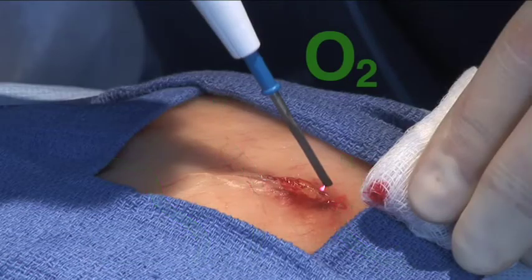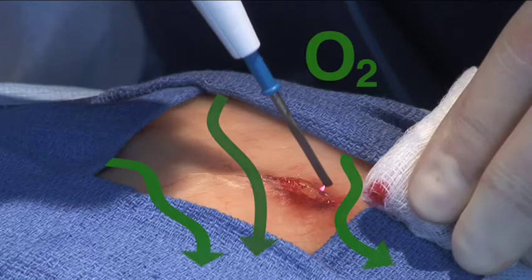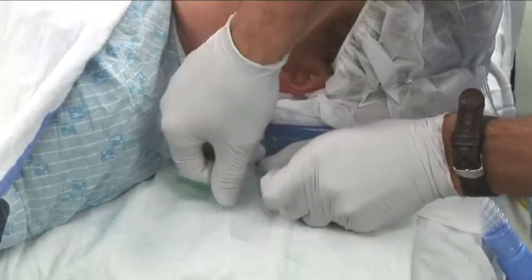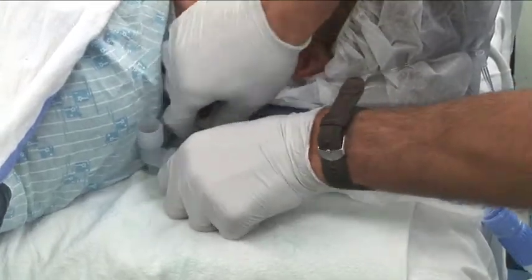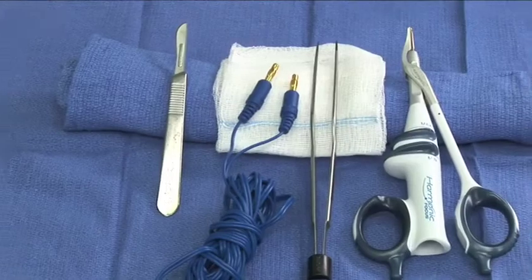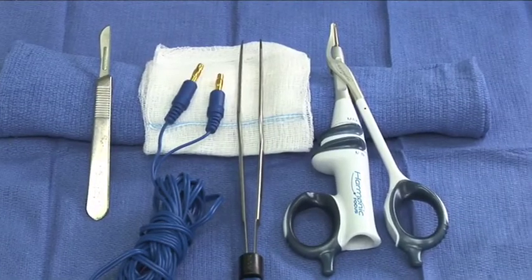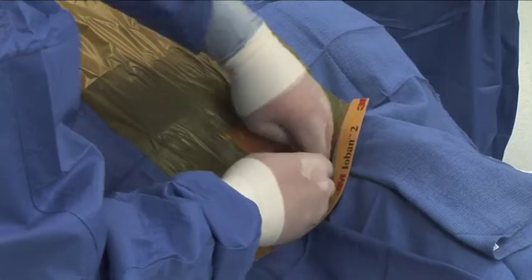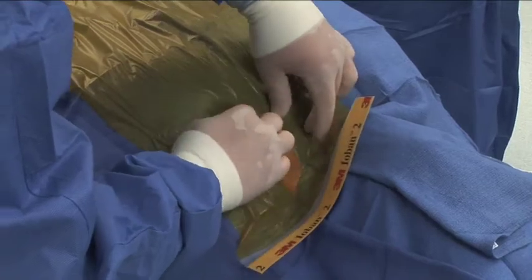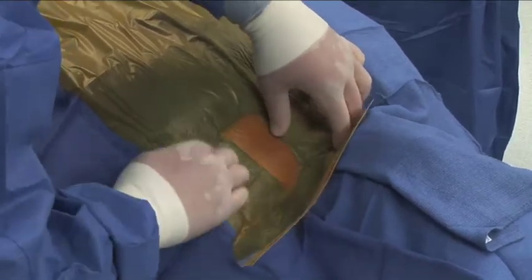Furthermore, the actual oxygen concentration at the surgical site is not known when using open oxygen delivery. You should always start with the lowest oxygen concentration required to keep the patient safe. The delivery of 5 to 10 liters per minute of air under the drapes can wash out excess oxygen. Use of alternate surgical modalities, such as a scalpel, bipolar electrosurgery or harmonic scalpel, can remove the ignition risk. Incised drapes may, in some cases, help isolate oxygen from the surgical site.